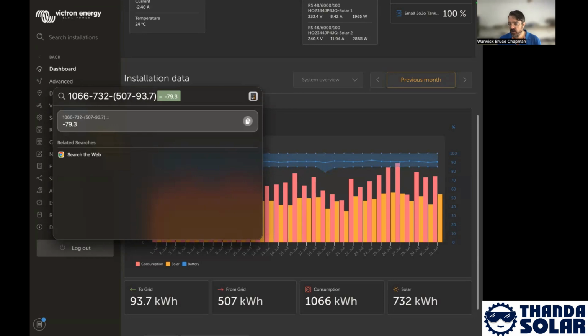Which means that the losses in this case, also a case where the site is feeding power into the grid, albeit less. In this case, the losses are 79.3 kilowatt hours. And if we take that 79.3 as a proportion of all the solar generated, we get 10.8% loss. So this would suggest to us certainly that this multi-RS site is performing better from an efficiency perspective than the Quattro-based site.